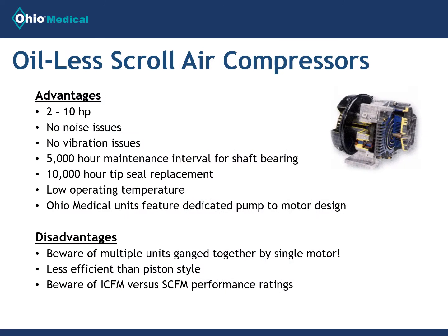The oilless scroll is, as the name implies, a completely oilless piece of machinery due to the self-lubricating PTFE seals. The dust seal on this protects against outside contaminants, and the radial cooling fan and cooling fins help lower the operating temperature. The serviceable bearings are external to the compression chamber, which is NFPA compliant, and the rotary design permits a true 100% duty cycle.